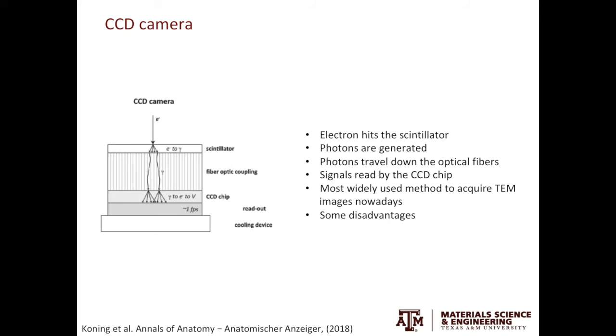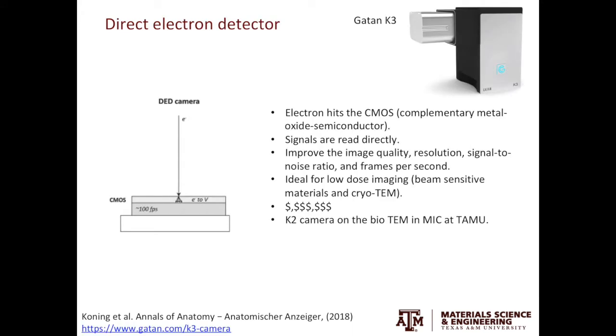To overcome this challenge, a new type of camera called the direct electron detector was introduced. In the direct electron detector, CMOS — the complementary metal oxide semiconductor — replaces CCD. When the electron beam hits the CMOS, it will be directly read as a signal. Compared to CCD cameras, the direct electron detectors offer improved image quality, resolution, signal-to-noise ratio, and frames per second. It is ideal for studying beam-sensitive materials such as lithium-ion containing materials and biological specimens.